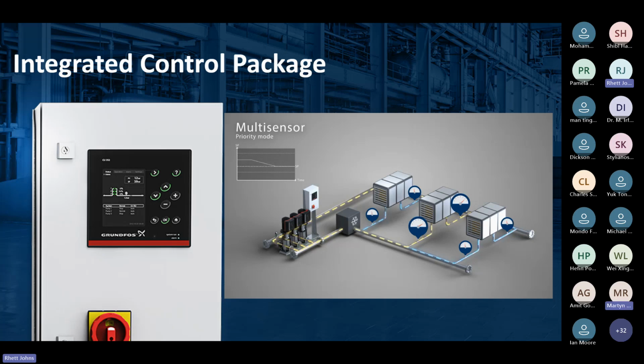The multiple pump controller that we see here is more seen, well, we work primarily in industry, this is seen on the utility side, where they've got big swings in production. They might not run a night production. They might have higher cooling demand requirements in the summer versus the winter. So here, when you've got big swings in your flow and big swings in your pressure requirements, you can then add these sorts of controllers and get a really attractive return on investment.